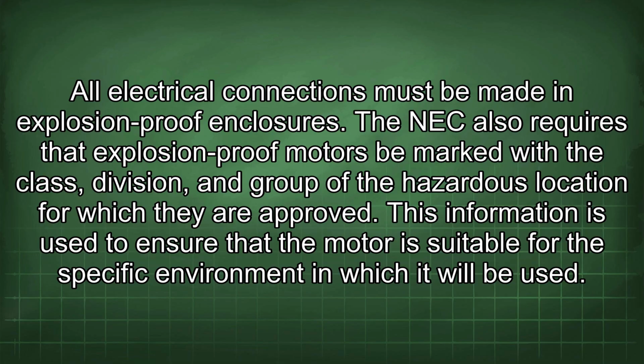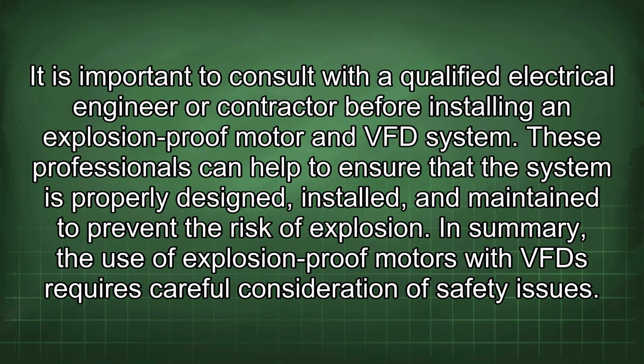The NEC also requires that explosion-proof motors be marked with the class, division, and group of the hazardous location for which they are approved. This information is used to ensure that the motor is suitable for the specific environment in which it will be used. It is important to consult with a qualified electrical engineer or contractor before installing an explosion-proof motor and VFD system. These professionals can help to ensure that the system is properly designed, installed, and maintained to prevent the risk of explosion. In summary, the use of explosion-proof motors with VFD requires careful consideration of safety issues.